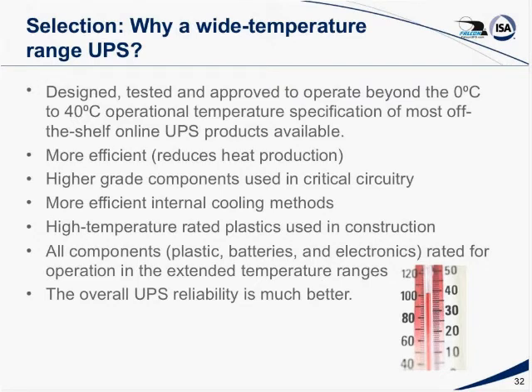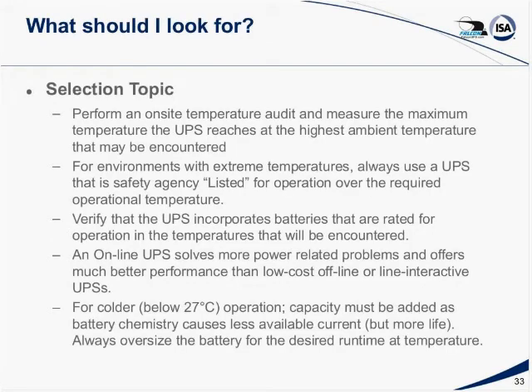All right, so what should I look for if I'm going to look for a wide temperature UPS? Well, first of all, you have to find out where you're trying to operate it. So you would do an on-site temperature audit and get your maximums and minimums, and of course you can research that data, since it's recorded in any number of places. But you want to make sure that you account for the highest ambient temperature that's going to be encountered and add some to that. If you do get a UPS for these conditions, make sure it is safety agency listed over this required operational temperature.